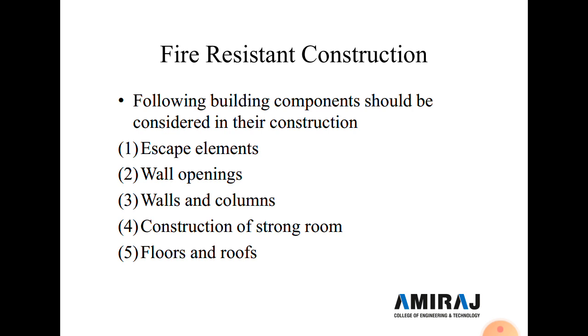And all walls in a building constructed should be plastered with a fire resistive mortar. And fourth is the construction of a strong room. So here especially the strong room is constructed as a safe deposit locker in a bank. The thickness of the walls, ceiling and floor of a strong room is at least 300 mm, constructed in cement concrete, and they are plastered with fire resisting plaster. And doors and windows should be fireproof, and windows and ventilators should be well covered with special steel square bars.